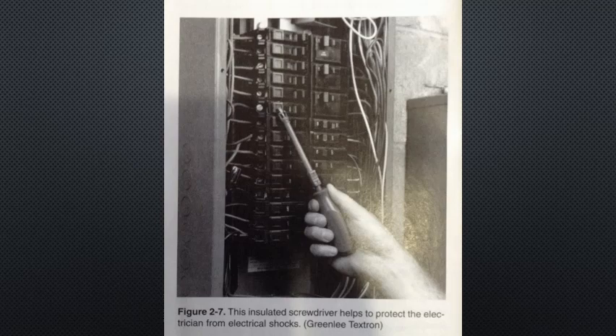Non-conductive ladders: fiberglass ladders should be used for electrical work; aluminum ladders should be avoided because they can become energized if they come in contact with an electric source. Perhaps the most important item is protective clothing — minimize the amount of exposed skin. Clothing resistant to flash flame helps prevent burns if a fault causes an explosion. Wear rubber boots or shoes with rubber soles, use rubber gloves whenever possible, and do not wear clothing with exposed zippers, buttons, or other metal fasteners. Never wear metal objects such as rings, wristwatches, or bracelets when working around electrical equipment, as these conducting items increase the risk of electrical shock.